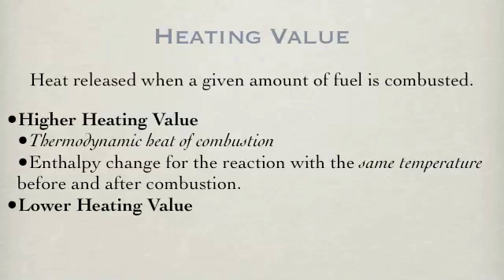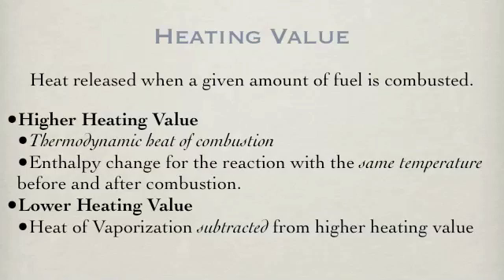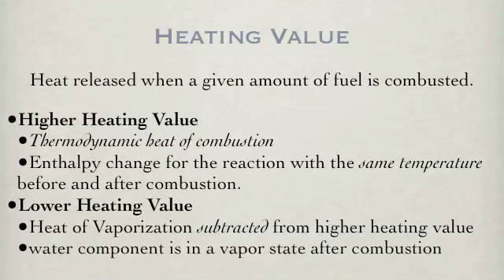The second value is the lower heating value. This is where the heat of vaporization is subtracted from the higher heating value. The justification for this is that the water is in vapor state after combustion, and this vaporization process requires energy.